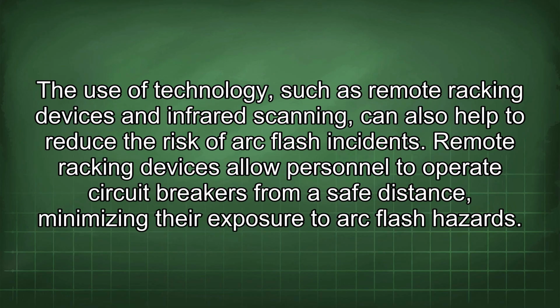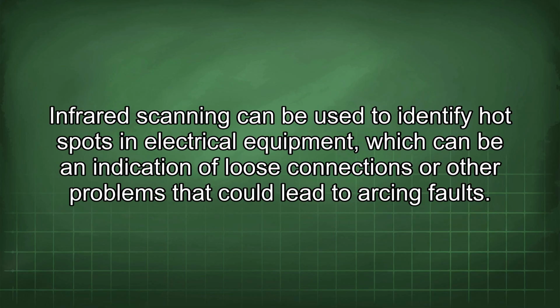The use of technology, such as remote racking devices and infrared scanning, can also help to reduce the risk of arc flash incidents. Remote racking devices allow personnel to operate circuit breakers from a safe distance, minimizing their exposure to arc flash hazards. Infrared scanning can be used to identify hot spots in electrical equipment, which can be an indication of loose connections or other problems that could lead to arcing faults.